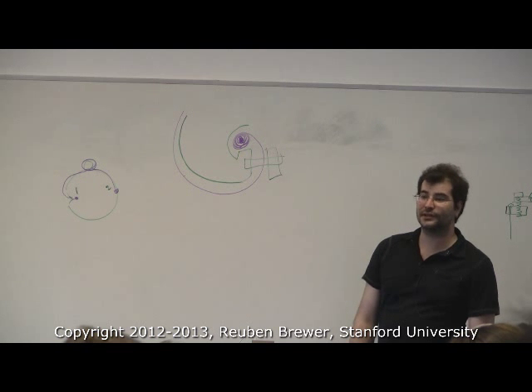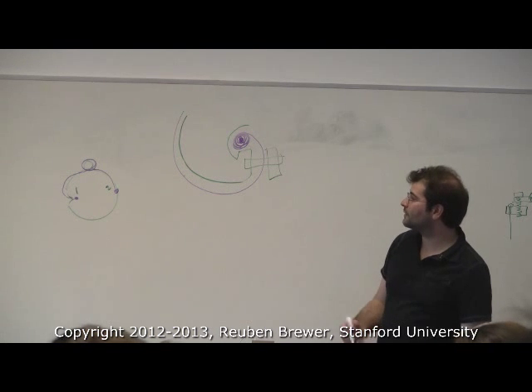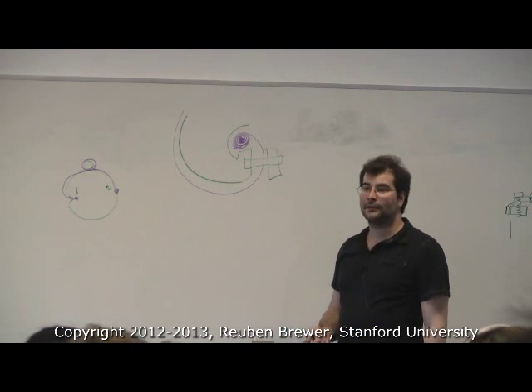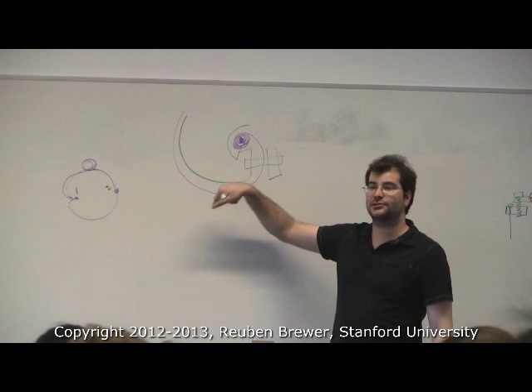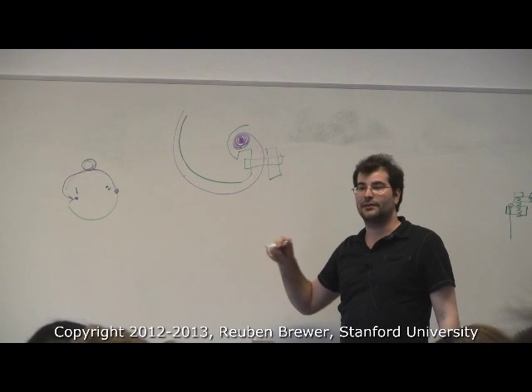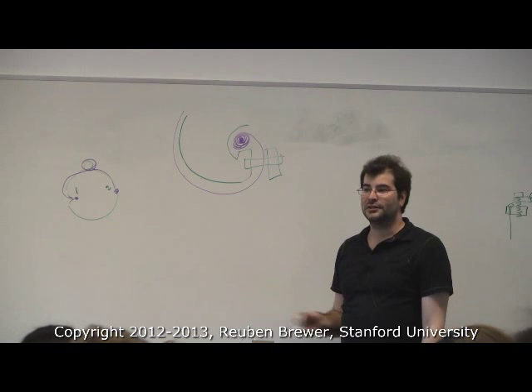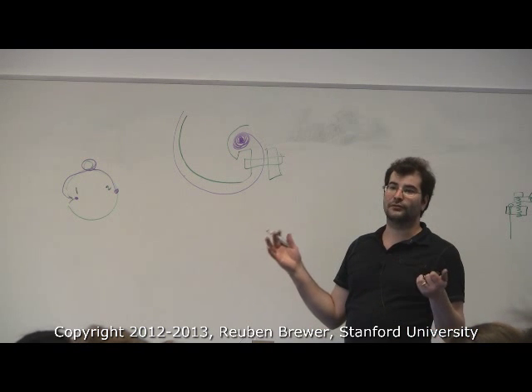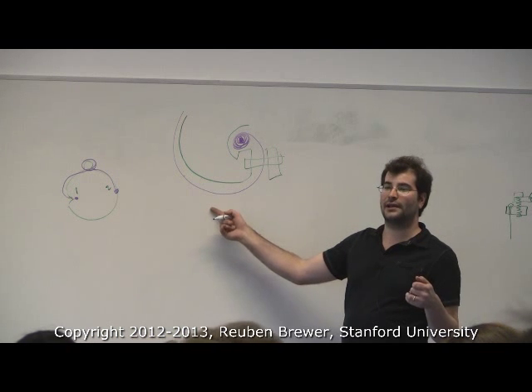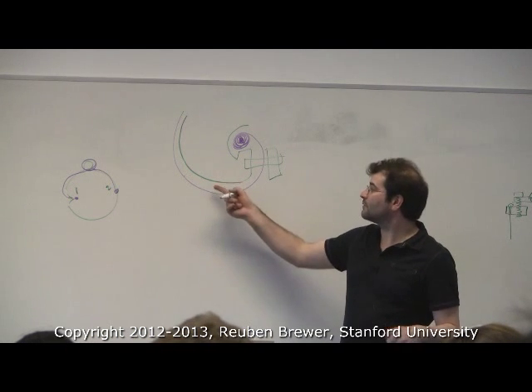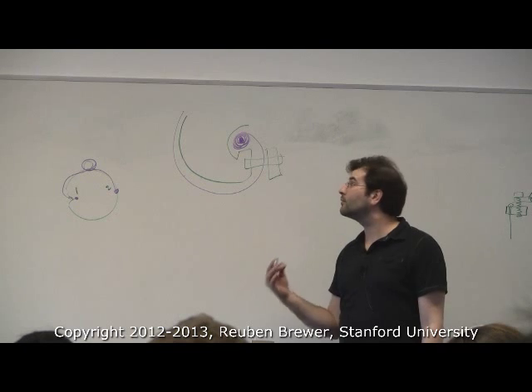It's usually the minimum bend radius recommended for that cable. Now, you're not going to be wrapping and unwrapping here, this is just going around once and then not moving, you're just tightening it there. But if you have to pick a number for some reason between razor's edge and not razor's edge, I typically just go with the minimum bend radius and keep it the same for the entire pulley.